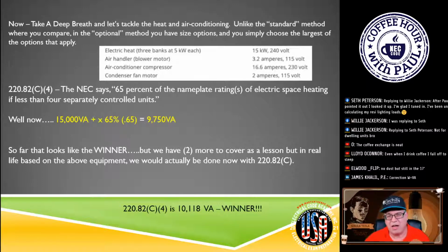So that's 9,750 VA. So far, it looks like that's a winner. So I can get rid of what I remembered for the AC because, again, it looks like I got a winner here.